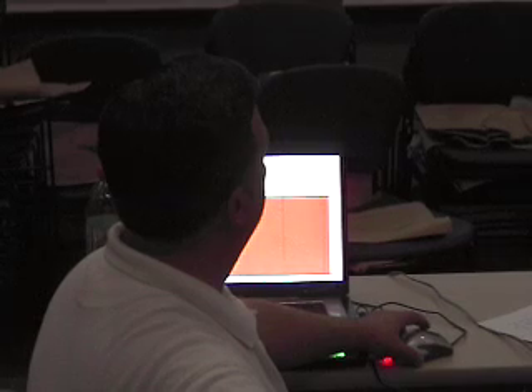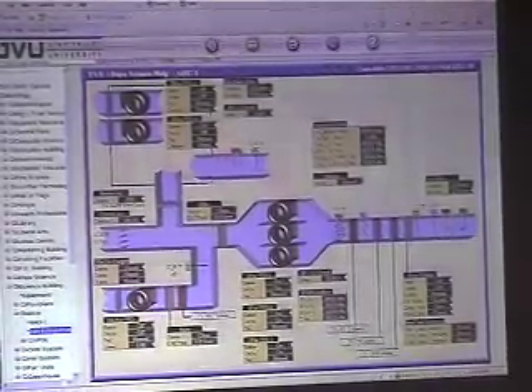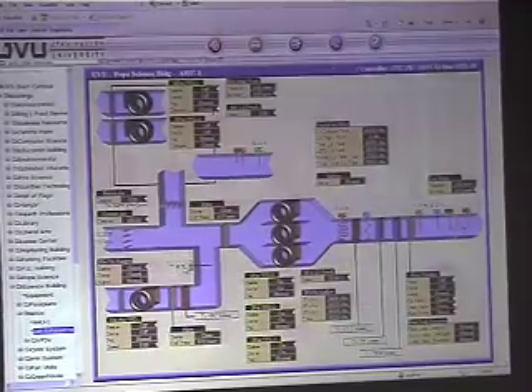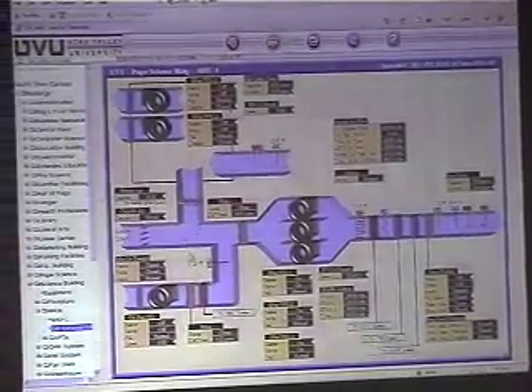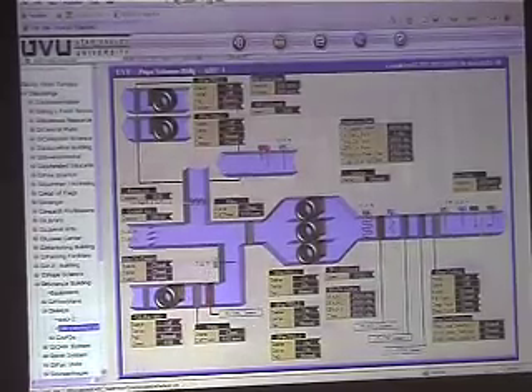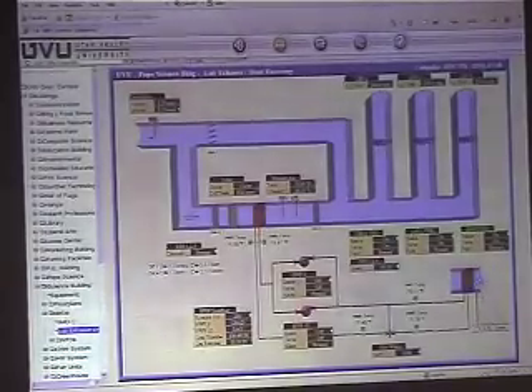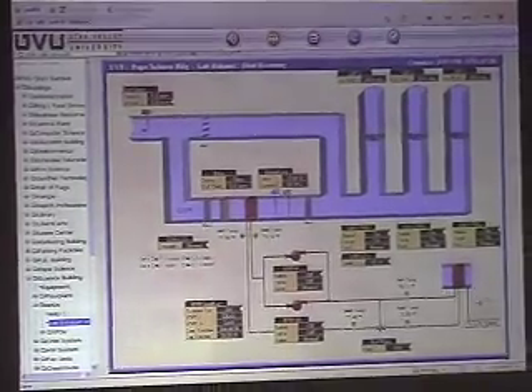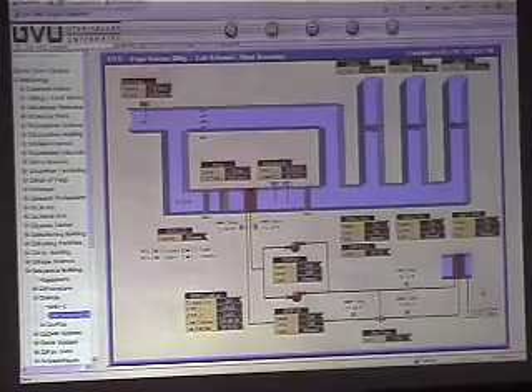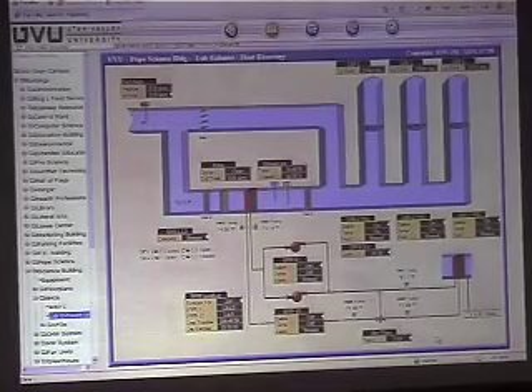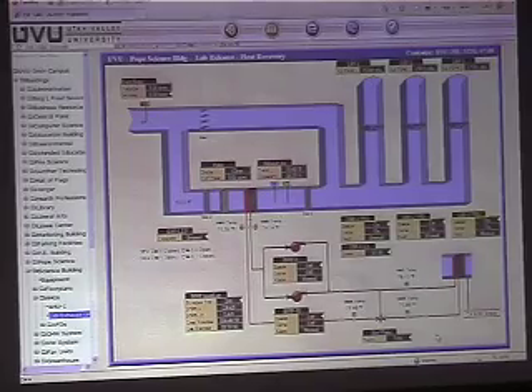The set point is at 48, is there a set point for it? Or is that the discharge or set point for the air? That's the discharge at this point right here. That's the set point for that. Oh, okay. That's a point I need to add to the screen. And actually, I'll even add this sensor right here, and I'll put the set point right here, so that you can see that that's what's controlling this valve. Okay.